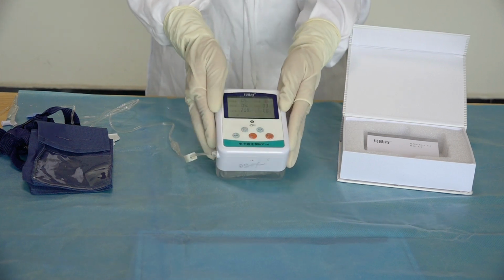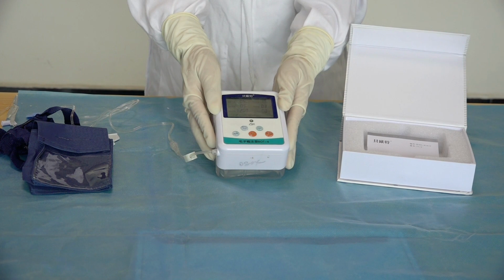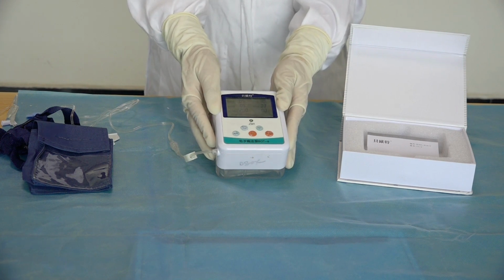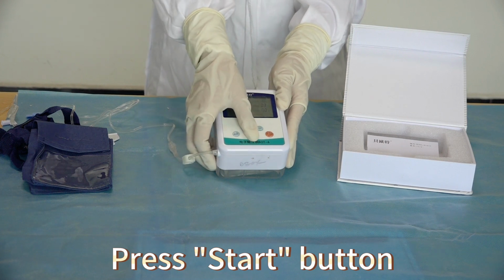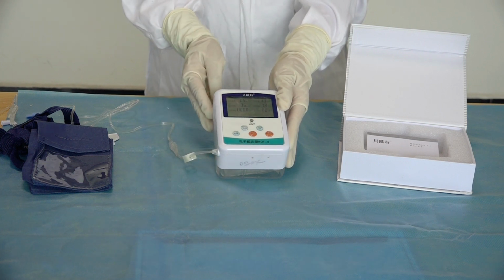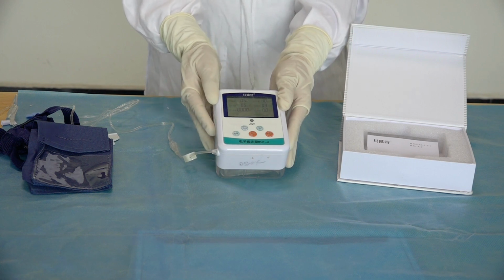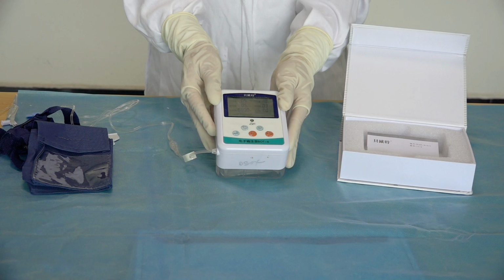Step 7. Start. After setting the flow rate, PCA volume, and PCA times, press the start button to make the machine running. At the same time, the electronic control component program locks the flow rate button, PCA button, power button, and start button. The word Run appears in the lower right corner of the screen and flashes, and the electronic control component enters the running state.